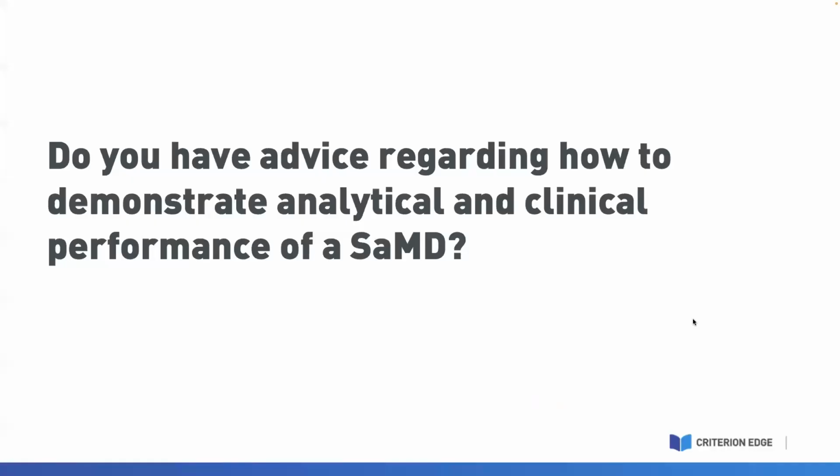So first question, Sarah, is do you have any advice regarding how to demonstrate analytical and clinical performance of a SaMD? Yes. So in our experience, the analytical performance is pretty straightforward. Think about how you validated the software in the first place. The clinical performance, though, that's going to be the tricky part.